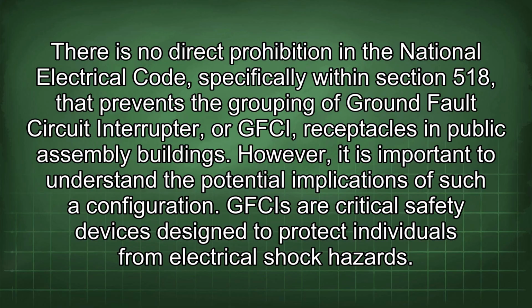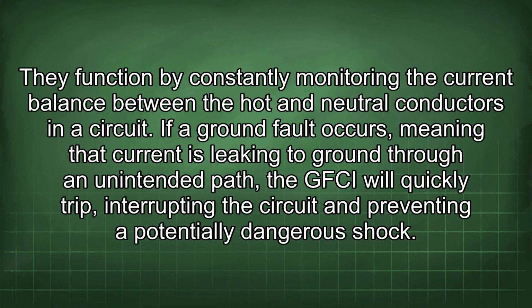GFCIs are critical safety devices designed to protect individuals from electrical shock hazards. They function by constantly monitoring the current balance between the hot and neutral conductors in a circuit. If a ground fault occurs, meaning that current is leaking to ground through an unintended path, the GFCI will quickly trip, interrupting the circuit and preventing a potentially dangerous shock.